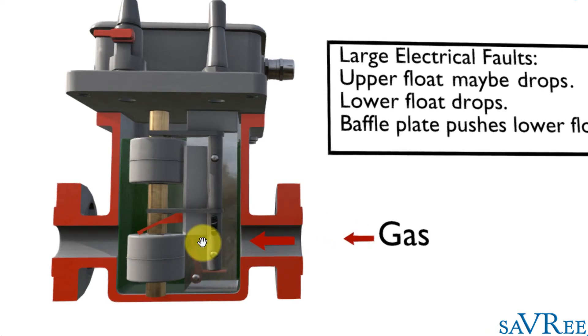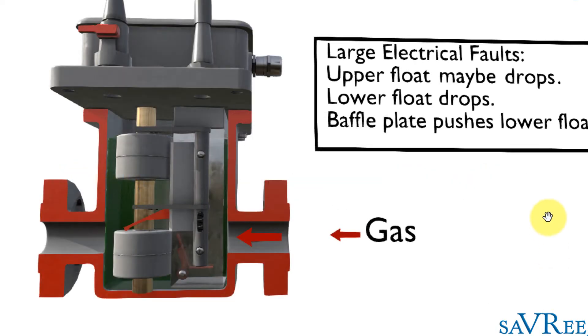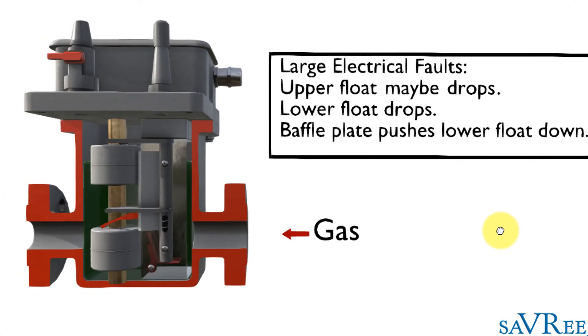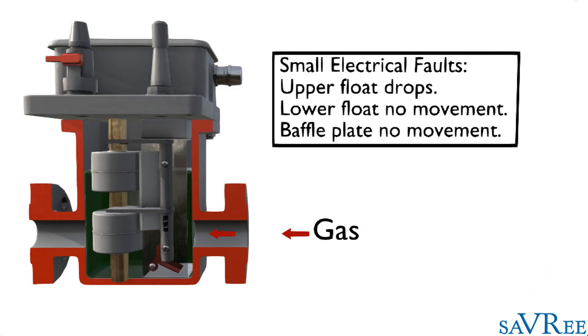However, there's other faults that we can also detect using the Buchholz relay. We're going to use different combinations of floats and the baffle plate. The baffle plate itself is now no longer used. It's only there to detect large electrical faults and to push the lower float down. So now we're going to use the upper and lower float.